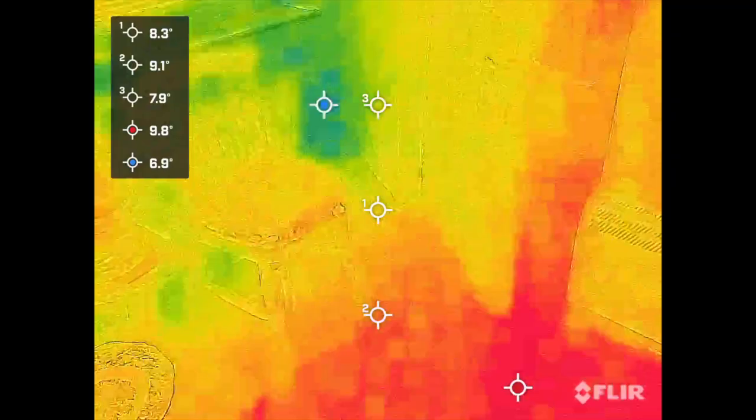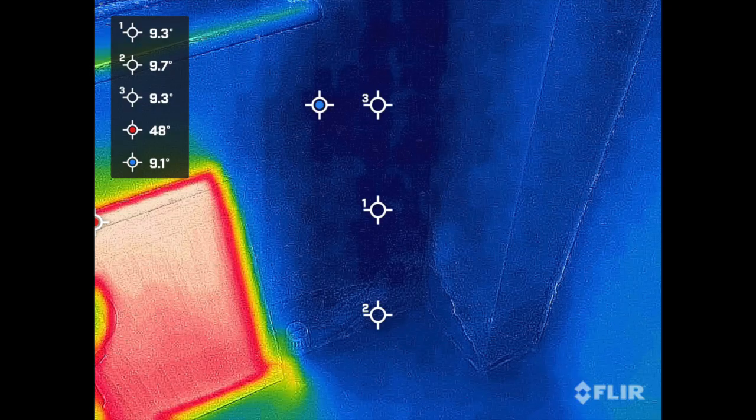As you can see, the temperature was low, but interestingly enough, the temperature of the wall remains at 9.1. You see that number 2 when you turn the heating on. So the heating isn't influencing that corner as much as you might expect. Now that's a short-term temporary thing, but even so, the key issue with this kitchen is obviously excess vapor in the first place, but also insufficient heat for the amount of vapor that you have, and insufficient insulation and airflow. So it's a combination of those factors.